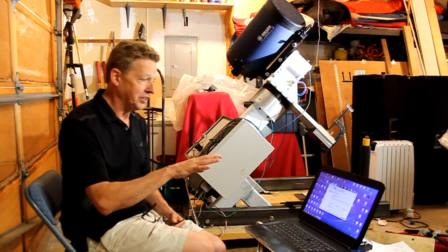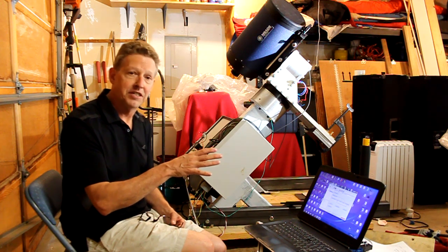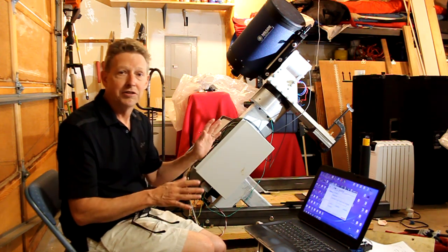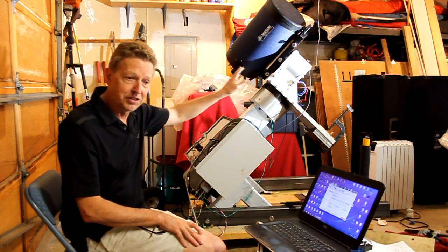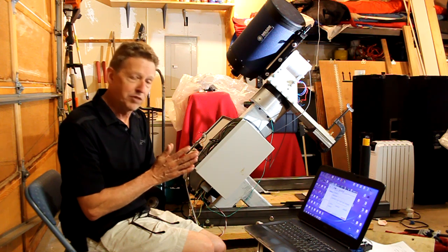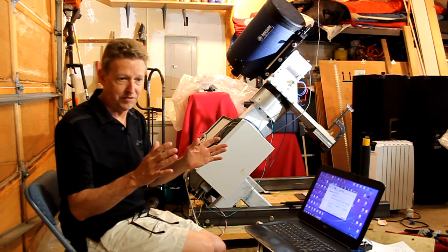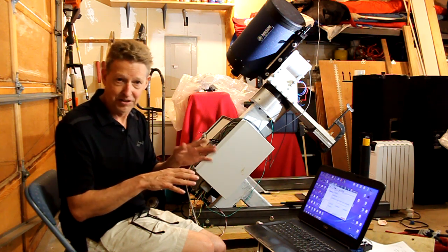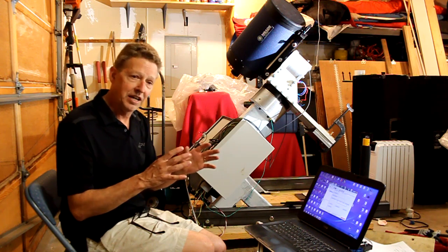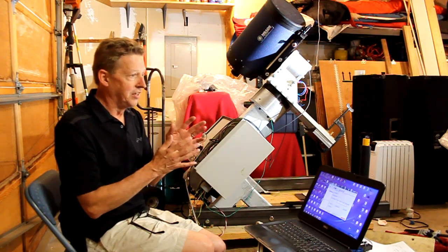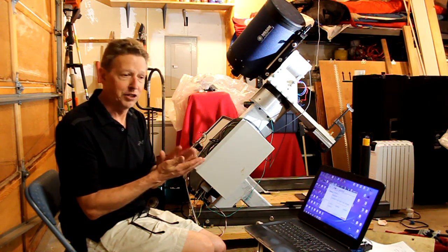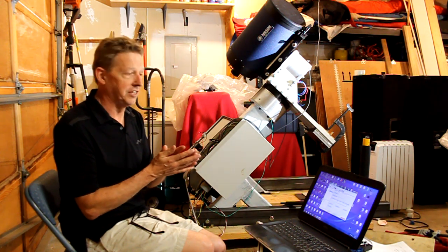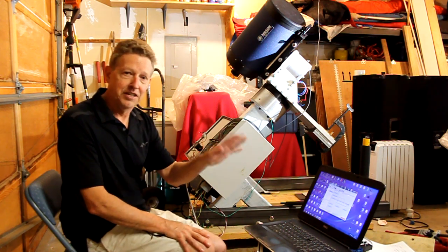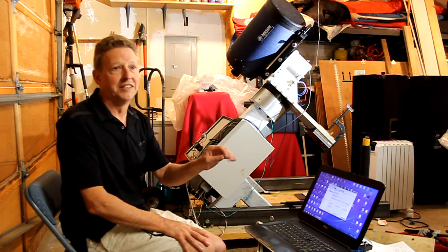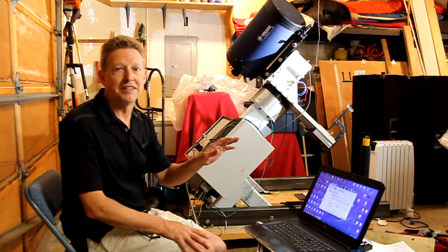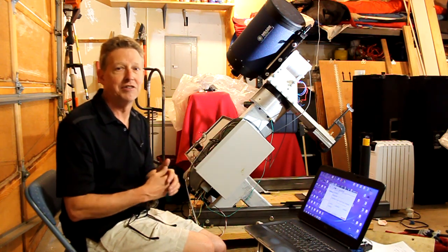One thing that I'm not going to show is another piece of tuning, which is the motor phase commutation. Now, with an absolute encoder drive, like this drive here, when the drive is powered on, the absolute encoder knows the exact angle of the rotor relative to the stator. To commutate a three-phase direct drive motor or brushless DC motor, you have to know the angle of the shaft relative to the windings. A sophisticated drive like this can automatically search and find that phasing. And that's one of the beauties of absolute encoders: once you have that phasing, it can be permanently stored in flash on the drive, and you never have to recalibrate it.